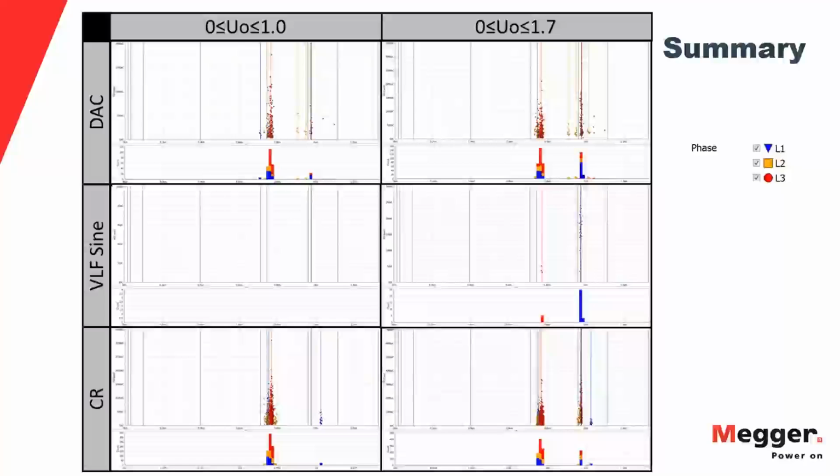However, what you do is try to gain scientific data for the risk assessment. After fixing those splices, or at least improving the quality, they are monitoring those cables a little more often than before to see if that spot develops into a more severe spot. So that was pretty much it.